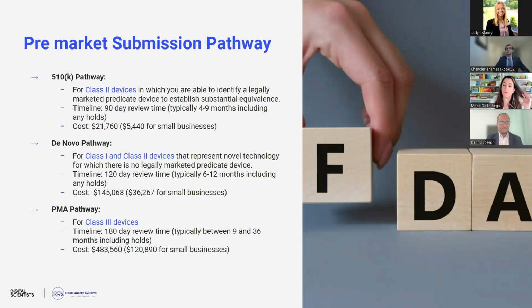The de novo pathway is for Class 1 and Class 2 devices that represent novel technology for which there's no legally marketed predicate device. So if you're unable to find a predicate device, odds are you'll have to go through the de novo pathway. A bit more time for this, 120 days or 4 months. We typically see 6 to 12 months, including those holds, just based off of FDA having to do a more extensive review as they aren't able to compare it to a legally marketed predicate device.